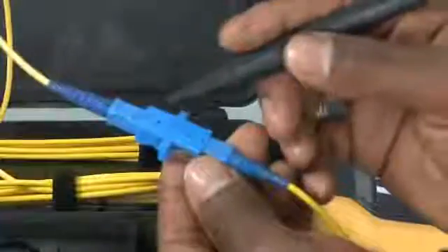The reason for the reflective peaks is the discontinuity that exists between a connector pair. There is a minute gap between the connectors. A splice has no discontinuity, and that's why it only has attenuation associated with it. Let's see what a cam splice may look like.